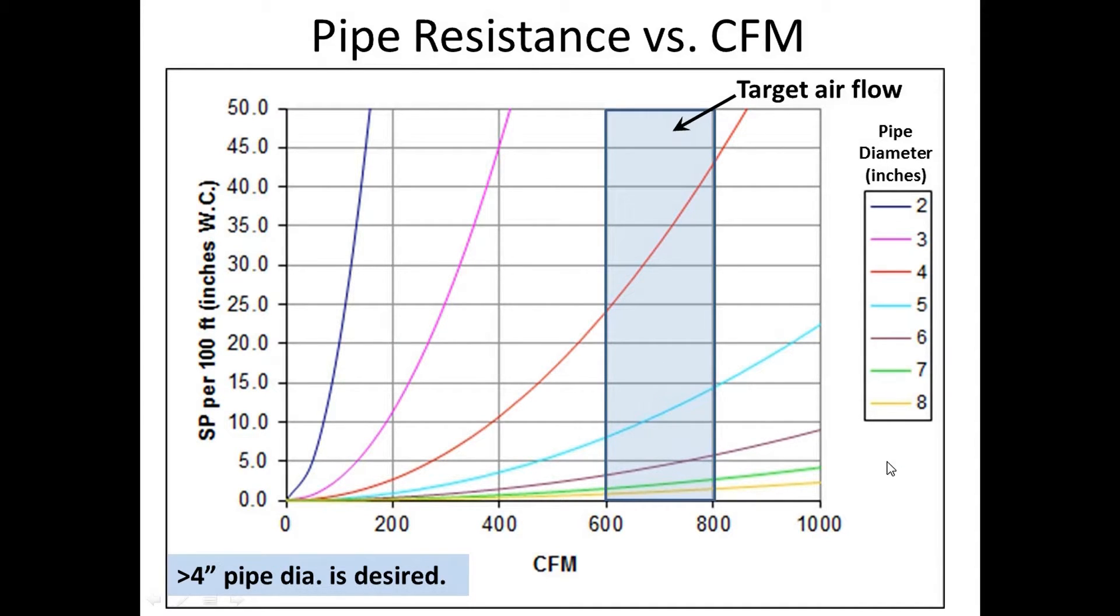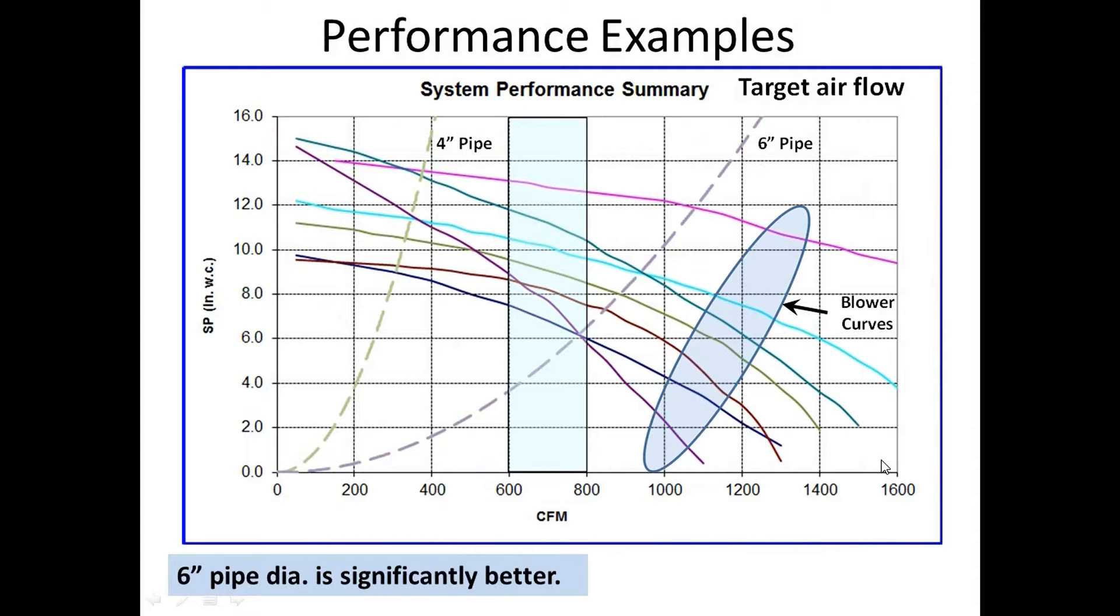Now you want to start talking about system performance. On this, you're combining both the blower curves, which are these lines here from the first graph we had, and the pipe resistance. So in this case I just settled on two pipe resistances: four inches and six inches.